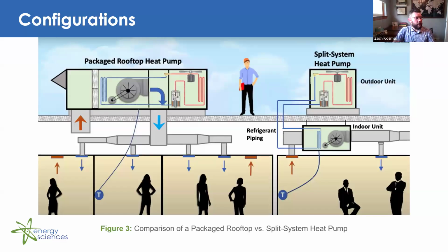So in this figure, we have examples of a packaged rooftop heat pump along with a split system heat pump, just to give you an idea of how these two systems may look in the real world. Both of these examples are air source heat pumps. So on the left-hand side, you have your packaged rooftop heat pump. This would look typically like your traditional rooftop unit. It's just a little larger typically because there's a few more components within that system. And then on the right-hand side is your split system heat pump, which that component on the rooftop there is a condensing unit or evaporator unit, depending on the heating or cooling cycle. But that looks very similar to your residential condensing unit that you may find outside of your home. And that refrigerant loop just connects to the coil that is within that air handler inside of the building. So these are just two examples of air source heat pumps.